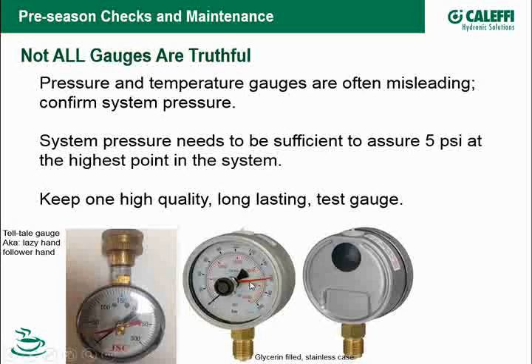Now you can buy them with this little extra needle in there, and it's sometimes called a lazy hand or a follower needle or a telltale gauge. So basically what happens when the pressure goes up, it pushes this needle along with it. So if you want to leave this on a job for a day where you think you're getting pressure spikes in a system, or you're wondering if the pressure is changing when you leave there, you can put this on, of course, turn this little knob here. It'll bring the red hand back down to this hand, and they'll move together. So I keep one like this on my truck, and this is a little cheesy gauge here. Not a slam on the company, but as far as the quality of the gauge. But this here, I have it with a hose connection. So I use this, as you can see, it's a high-pressure gauge.